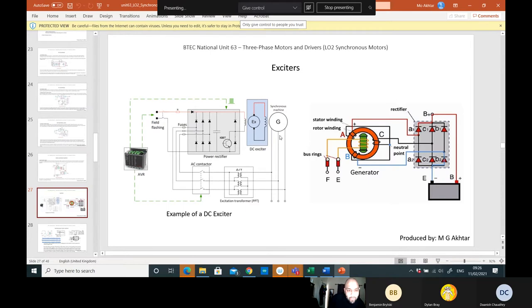What you've got is quite clever. You take the power that you're going to use for your synchronous motor, because people realized with a DC excitation system, you have to supply a separate DC voltage source to the slip rings, to the brushes which attach to the slip rings. So you're using two different power sources: the AC three-phase power source to begin the power for the synchronous motor, because it is a three-phase motor, for the stator windings, and a separate one for the slip rings. So why not just use one power source? Makes a lot of sense.